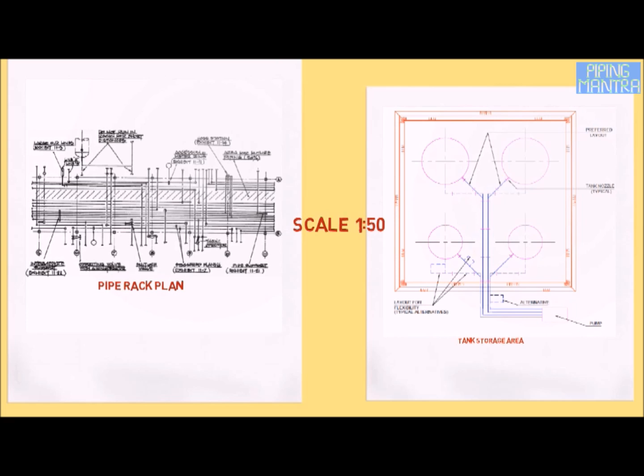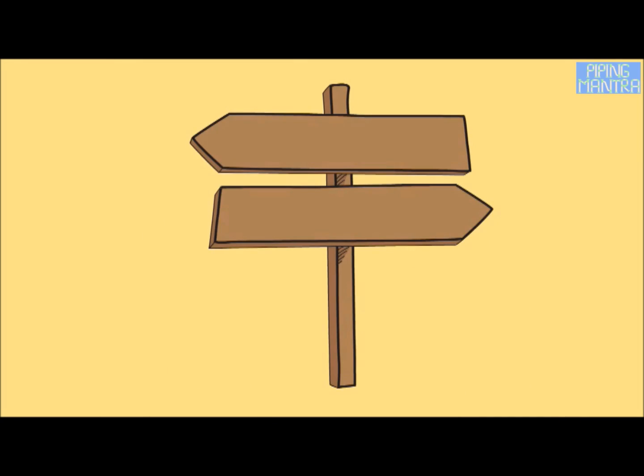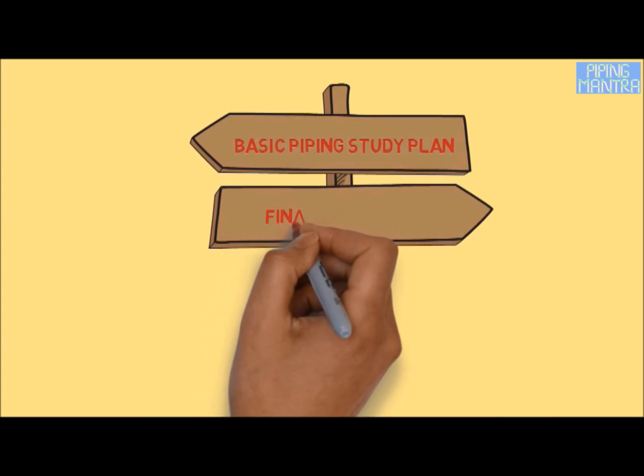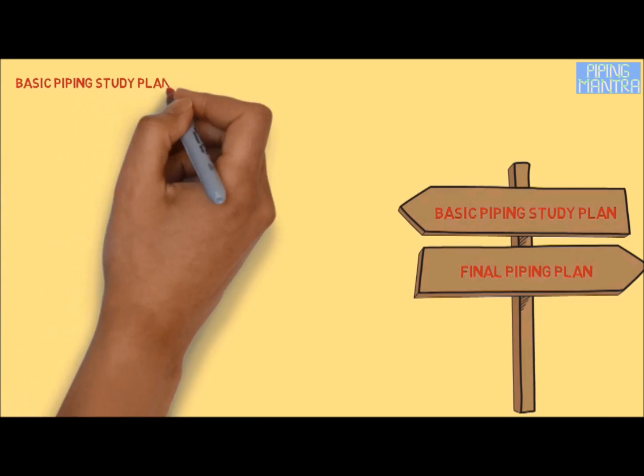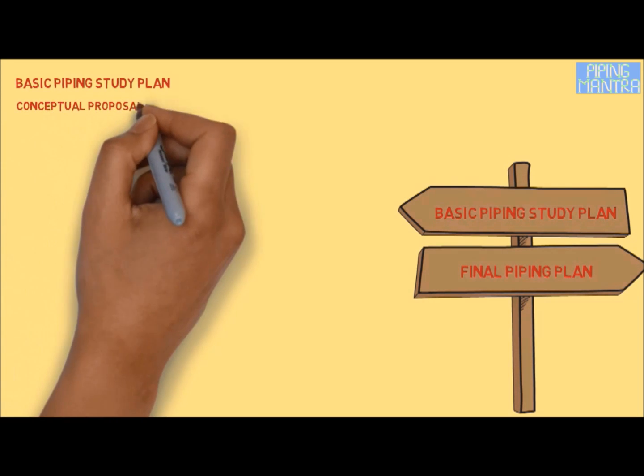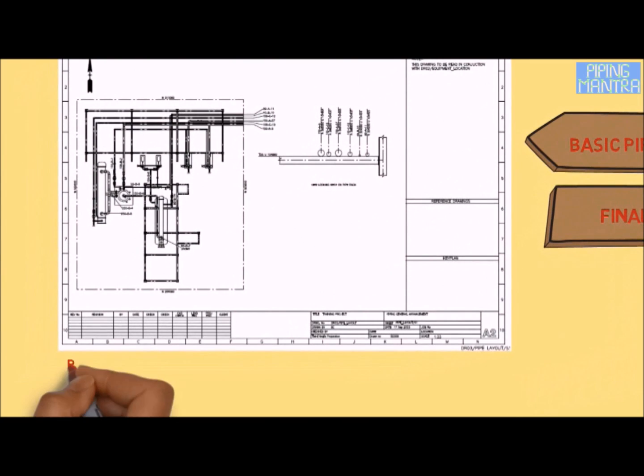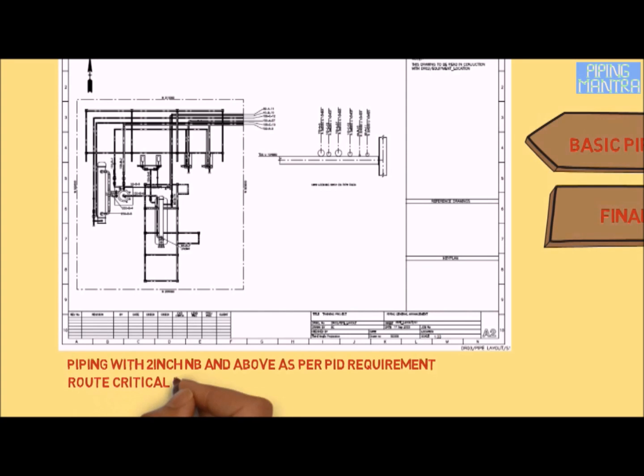Usually, flow-wise plans are made and local section views are given whenever elaboration is required. Normally piping plans are prepared in two stages: one is a basic piping study plan and another is the final piping plan. The basic piping study plan is a conceptual proposal with necessary sectional views, showing pipes of 2 inch and above as per the P&ID.